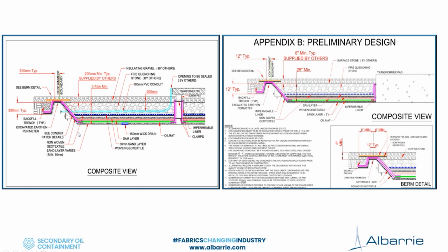But again, you can either have them running below the containment, or in the case of a grounding grid, it could come over the pad and lower back down inside the containment here. We're showing here a pad being supported by piles. You can also have a full depth concrete pad and we can strap to it. It doesn't have to be full depth. It could be a shallow pad as well, and we would strap to that. We need a minimum of 8-inch thickness in the pad itself.